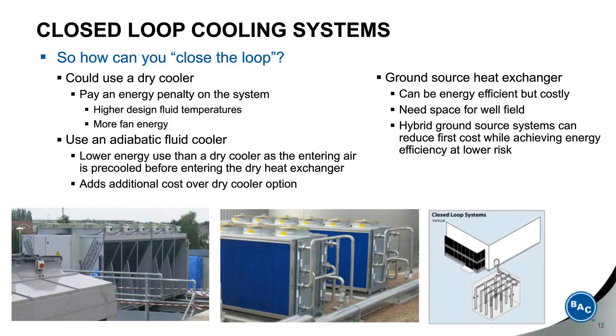At minimum, I recommend that consulting engineers consider putting in connections so that should the well field heat up beyond what can cool the building, or that perhaps some of the wells are not properly grouted, you can then put in a rescue fluid cooler and connect it easily into the system in the future. So that little bit of extra piping can provide an insurance policy in the future.